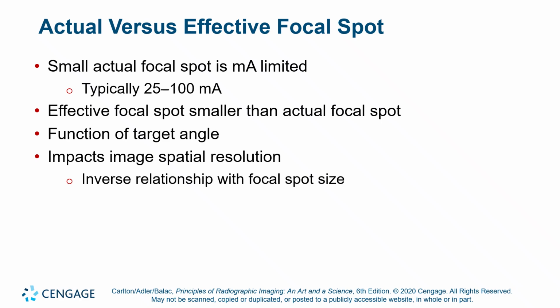I do think it's 0.6 millimeters for the small one and 1 millimeter for the large one. Okay. Yeah, he does give a range here on the bottom of page 86 in the Carroll book: diagnostic tubes are available with focal spots of 0.1 all the way up to 3 millimeters. The greater the target angle, the larger the focal spot.